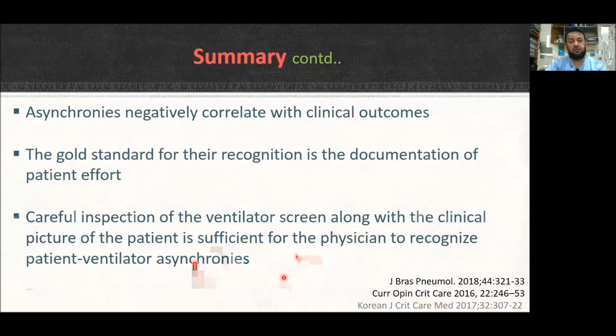So thank you all. You said in double trigger the tidal volume is high, but in auto trigger and reverse trigger, what will happen in tidal volume? Auto trigger and reverse trigger also there will be high tidal volume delivery, but in auto trigger there will be high minute volume delivery because there will be too much respiratory rate, and as a result there will be too much minute volume delivery. So if you allow too much minute volume delivery, then there will be carbon dioxide washout. What we do then? Deep sedation or no? If there is too much auto triggering, you have to adjust the trigger appropriately, and you have to find out the cause of auto trigger. Whether there is water in the circuit or leak in the circuit, you have to ensure that. Leak has to be reduced, circuit water has to be removed, and if there is secretion, that has to be suctioned out.